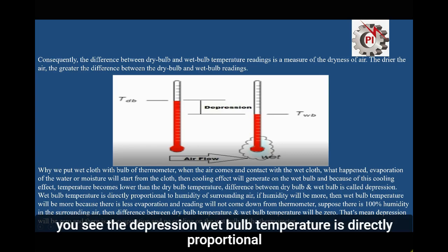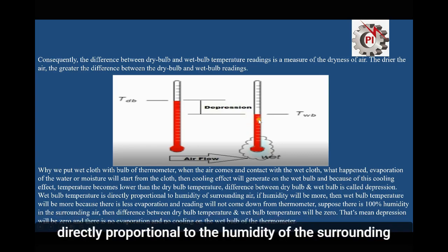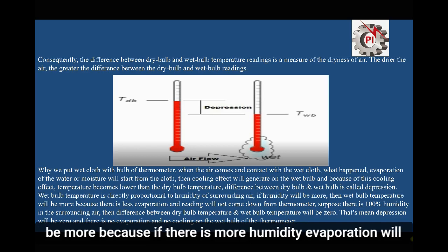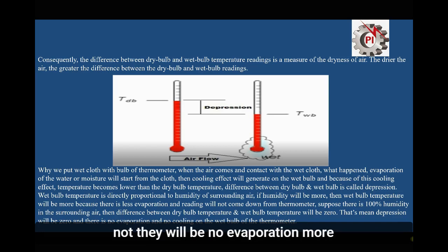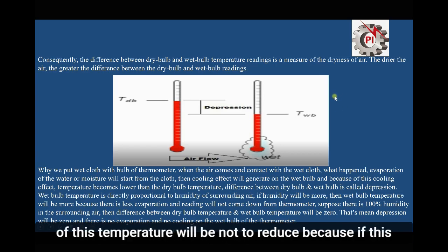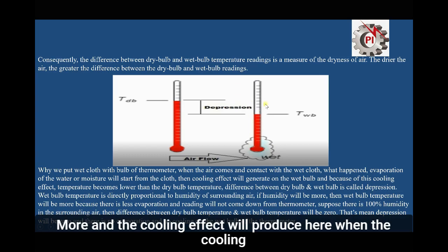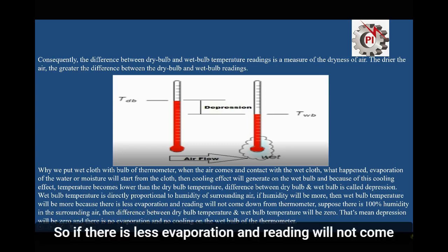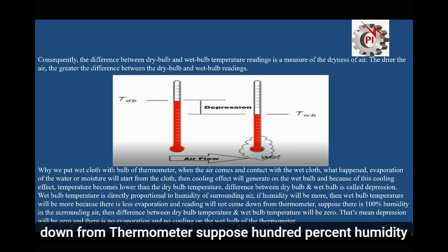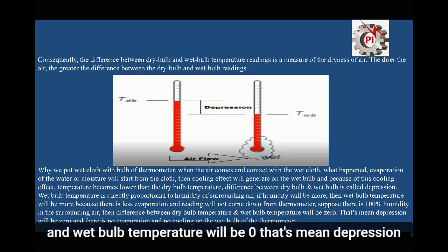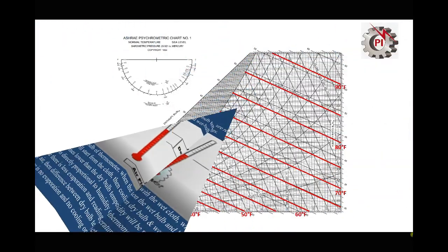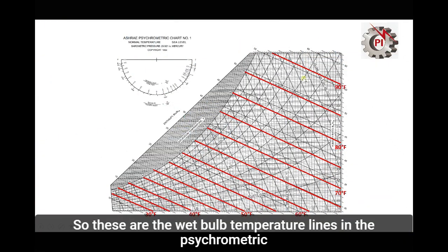Wet bulb temperature is directly proportional to the humidity of the surrounding air. If humidity is more, evaporation will be less, so the cooling effect will be less and the temperature will not reduce much. If the air is drier, evaporation happens more and the cooling effect is greater. Suppose there is 100% humidity — the difference between dry bulb and wet bulb temperature will be zero, meaning no evaporation and no cooling on the bulb. These are the wet bulb temperature lines in the psychrometric chart.